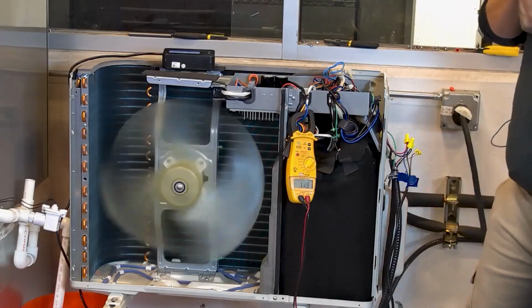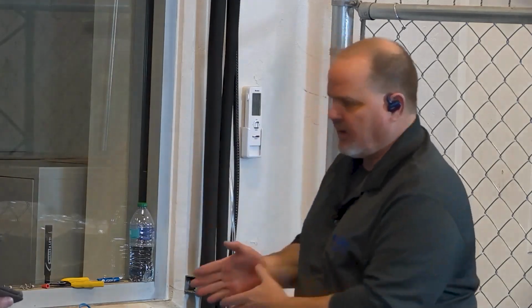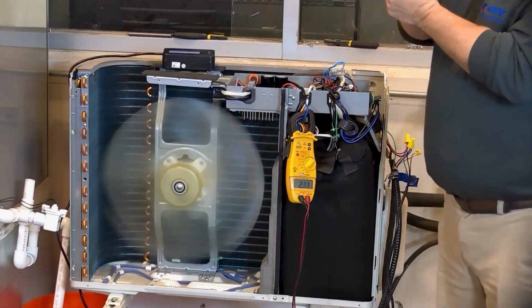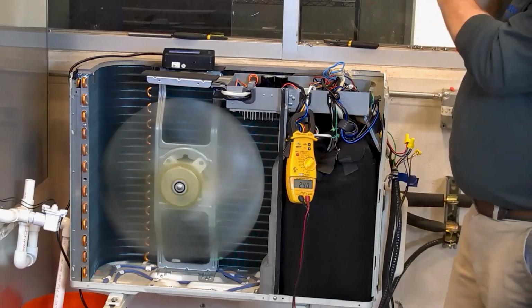If the machine runs for a while and then all of a sudden gives you an H5 or an H7, it could be caused by refrigerant flow. Because you've got to remember, the service tool gives you condensing coil temperature and evaporator coil temperature, and you can convert that to pressures. But we don't have a high and low side gauge. But if you've got a flow problem and we can't push that pressure off our high side through our metering device and feed that evaporator, okay? So you've got a restriction, right? Maybe the EV is not open right. I don't know.